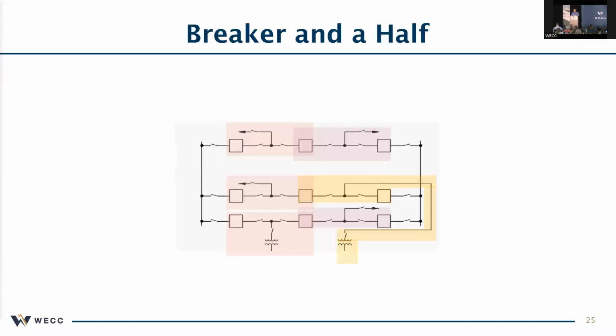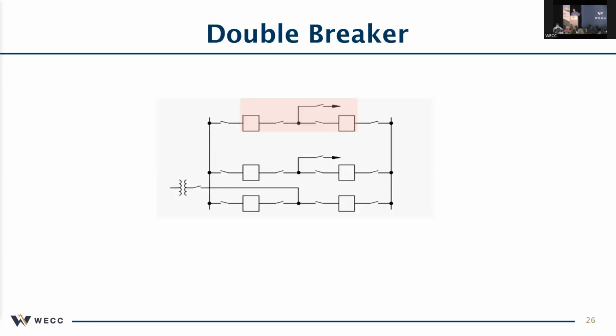Same thing goes here. If you look at each one of these facilities, if we're doing a sample of each facility by going on this breaker to breaker method, there's enough overlap that we've essentially covered that whole bus, except for the main pieces on the end, which is low risk of being a limiting element. Double breaker, same story. Still consider both of the breakers there.